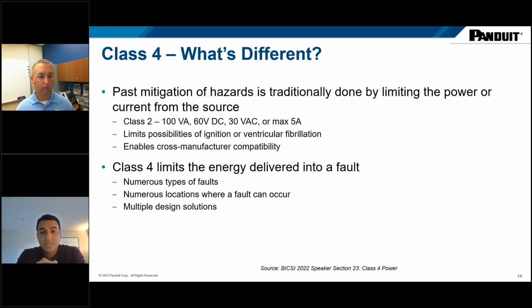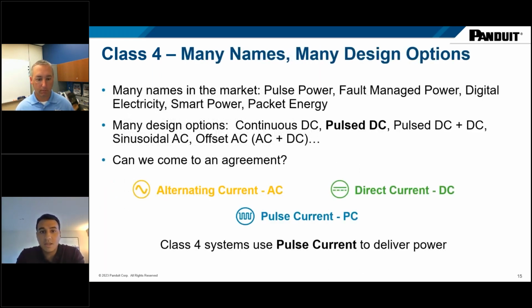Class 4, however, limits energy delivered into a fault, and there is no one way to design a class 4 system. There are many types of faults that you need to adhere to or detect, and different locations where these faults could occur. So you'll see in the industry today there are many names for class 4 and many design options. In terms of names, you'll hear of pulse power, fault managed power, digital electricity, you name it. There are a lot of names and maybe some confusion around this.